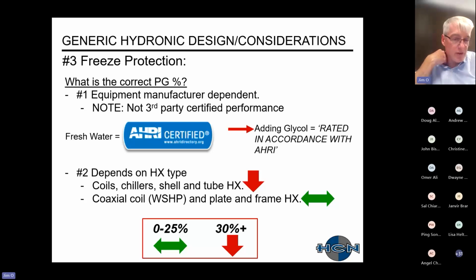And then once again, just a personal observation from selecting equipment over the years and years, if you can keep your glycol percentage between 0 and 25, you're really not tapping into too bad of a derate. It just seems that once you get to 30% or higher, the performance really takes a big hit, and often makes it difficult to achieve capacities and leaving air temperatures. So anyway, just an opinion or a tidbit of my experience, that if people could live with 25% versus 30%, the performance of your system would operate a lot better.